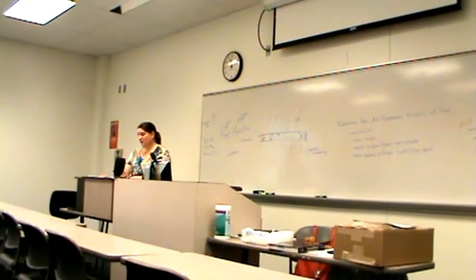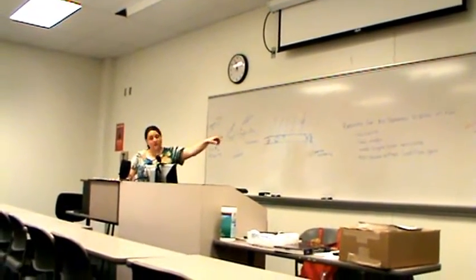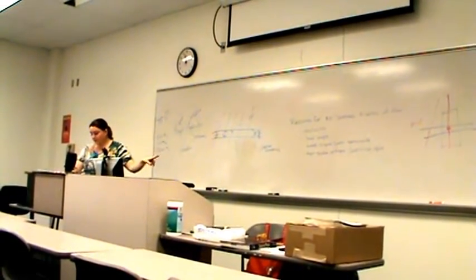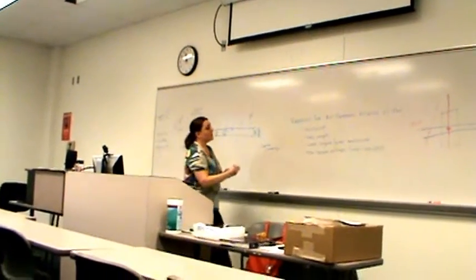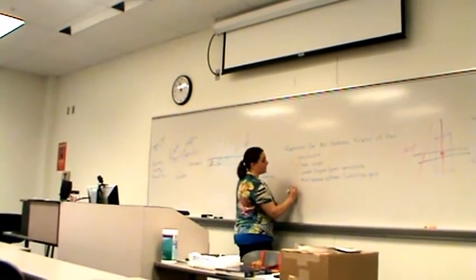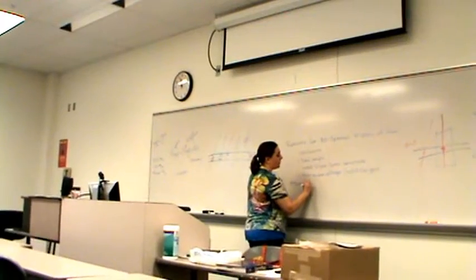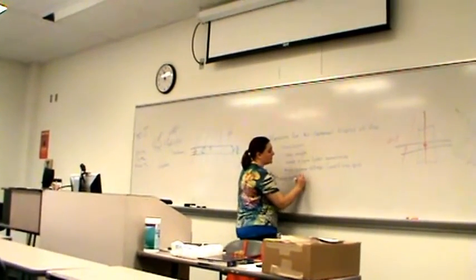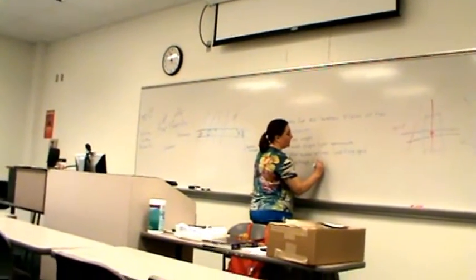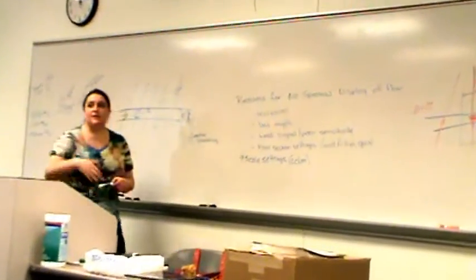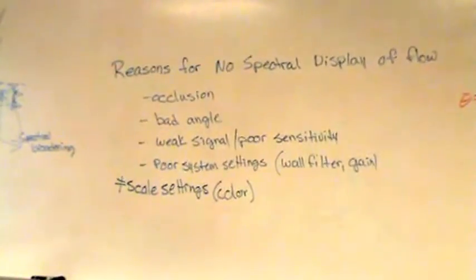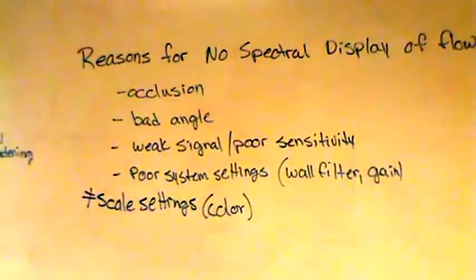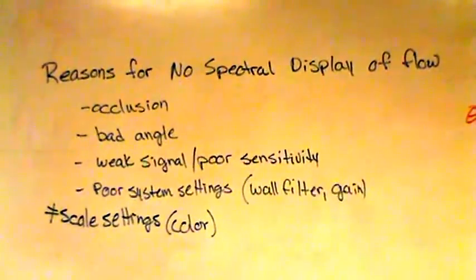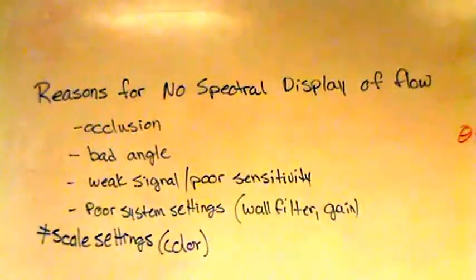Okay, that's really it. All of these reasons for no flow also are present with color. The only thing different with color is, and it works a little bit for spectral as well, scale settings, but more for color, because our scale settings in color are related more to the wall filter. So if my scale setting is too high with color, I'm going to end up filtering out the flow too. So whenever we're trying to detect low flow with color, we really have to turn the scale down.